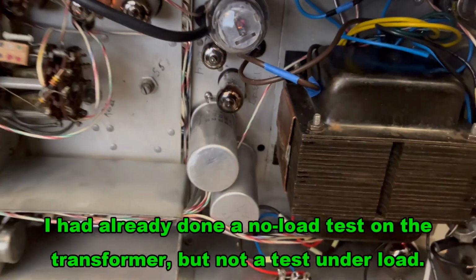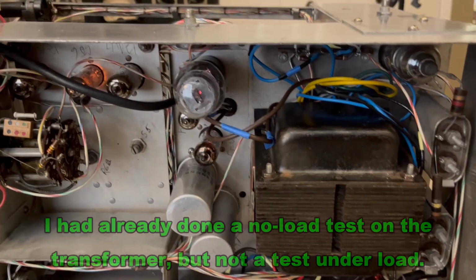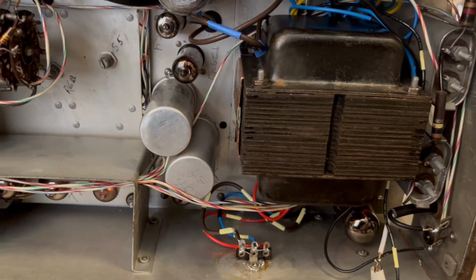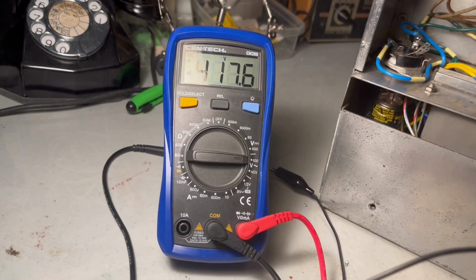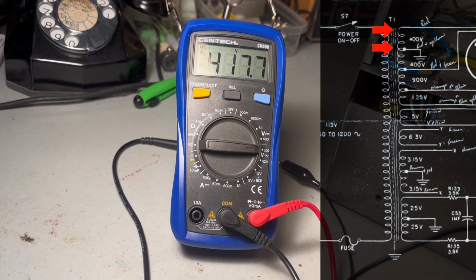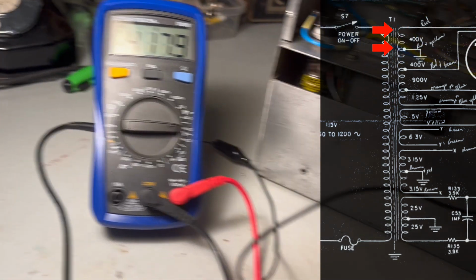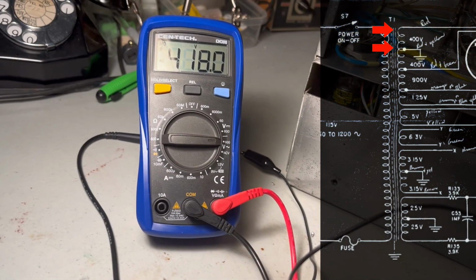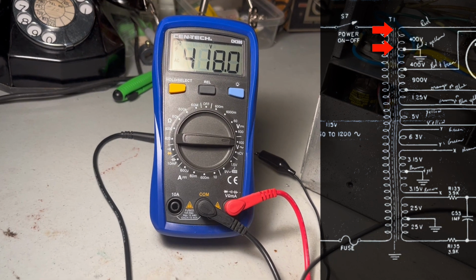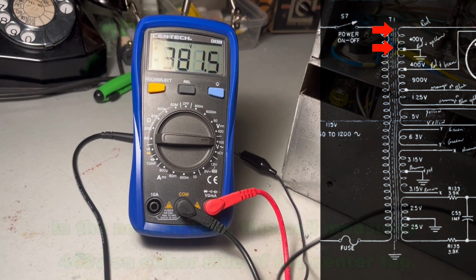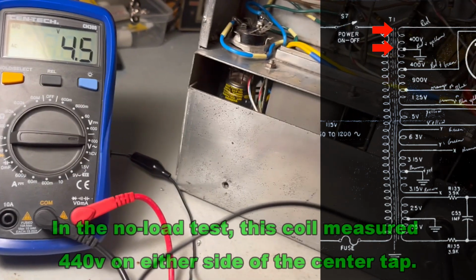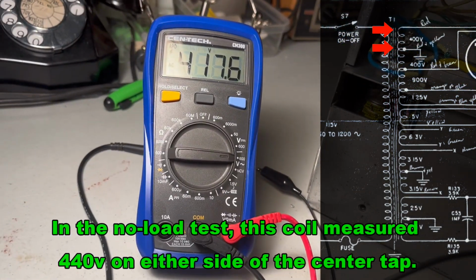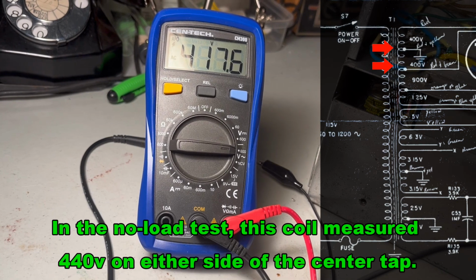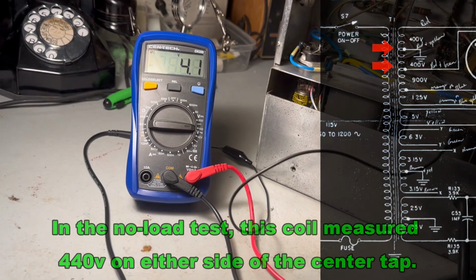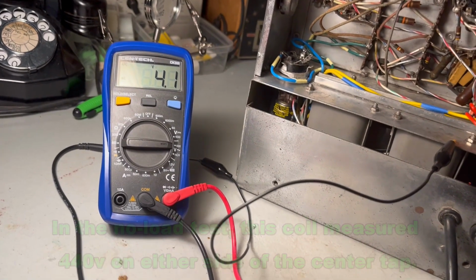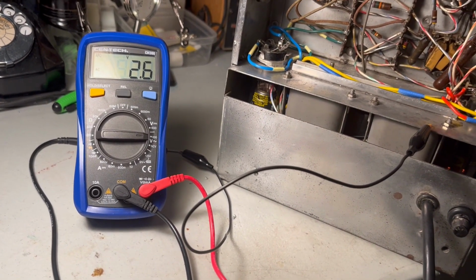But really, I do need to start from the very beginning and start taking voltage measurements. Taking a reading here on one of the high voltage leads to ground, which is where the center taps are tied off to. I'm reading 418 volts on what I call the positive side of that transformer. The other side is also 417, so it's pretty close to what we're looking for. I'm going to shut this thing off and move to the next reading.